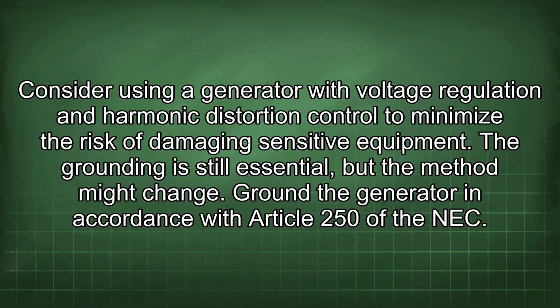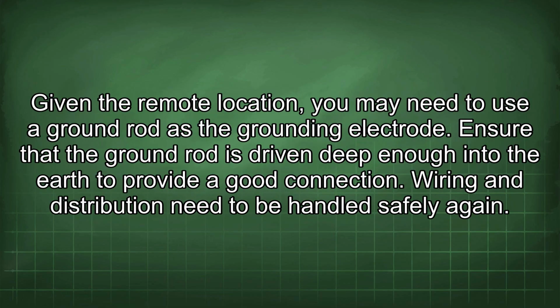The grounding is still essential, but the method might change. Ground the generator in accordance with Article 250 of the NEC. Given the remote location, you may need to use a ground rod as the grounding electrode. Ensure that the ground rod is driven deep enough into the earth to provide a good connection.